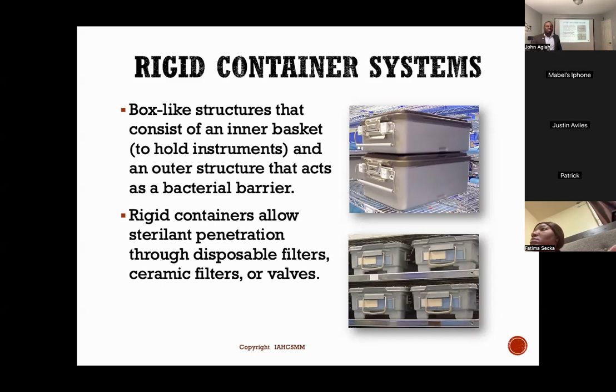Rigid containers allow sterilant penetration through disposable filters, ceramic filters, or valves. The rigid container is solid, it's metal, well, yeah, for the most part. And there may be holes underneath it, and there may be holes on the lid. The holes are where we place the filters. The filter is what filters microbes. It's also the same spot where steam comes through from the sterilizer to sterilize the contents. That is where steam exits as well, okay? Water exits through the filters as well. And after sterilization, the filter is what prevents microbes from coming inside to compromise the tray.